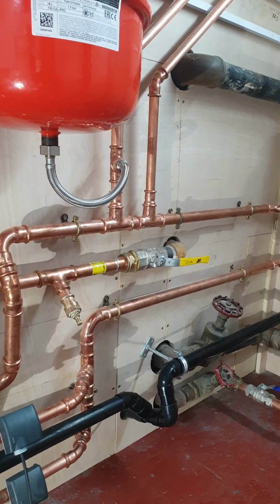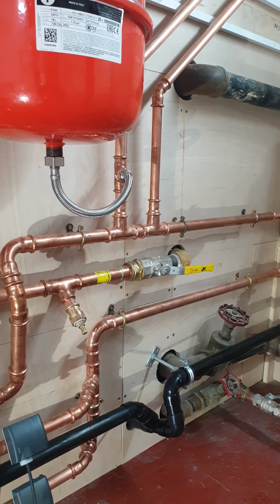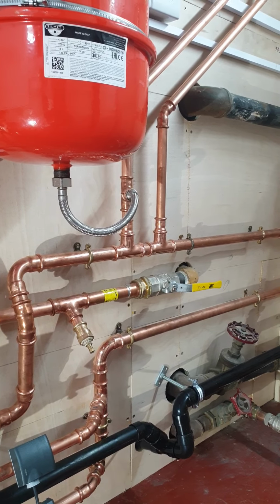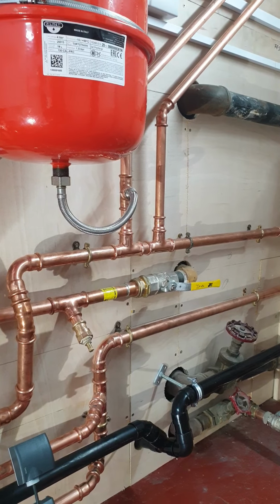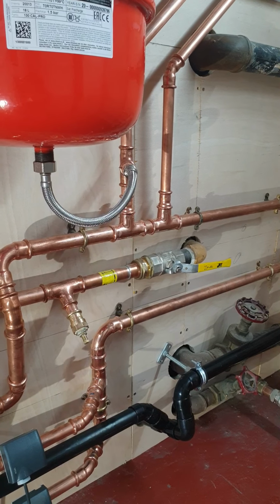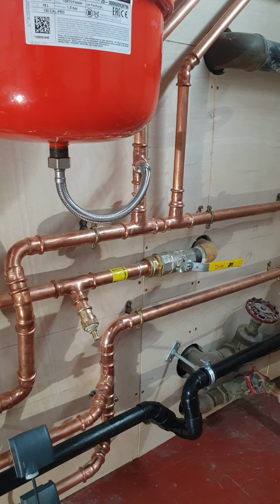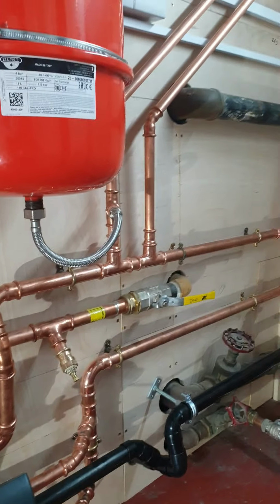Now this is interesting. Look, this is actually an open vented system. There's an expansion tank mounted on the side of the building, external, where it can freeze up. So the system's under gravity, and we were not offered the opportunity to change too much. We only got the plant room. So we brought the cold feed and expansion into our system. But these aren't actually acting as our primary safety devices for this system, because they're going to freeze up, and when they freeze up there'll be nothing.